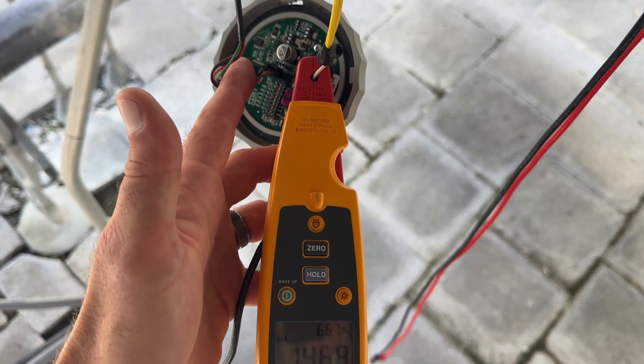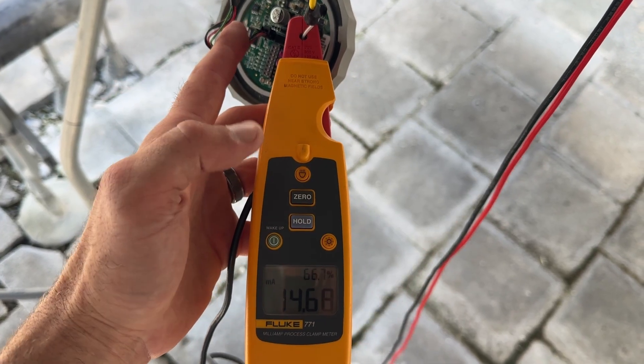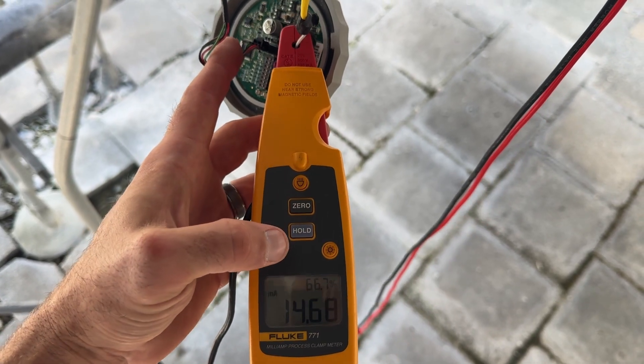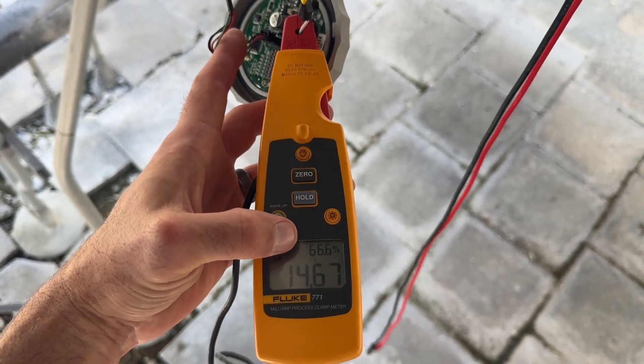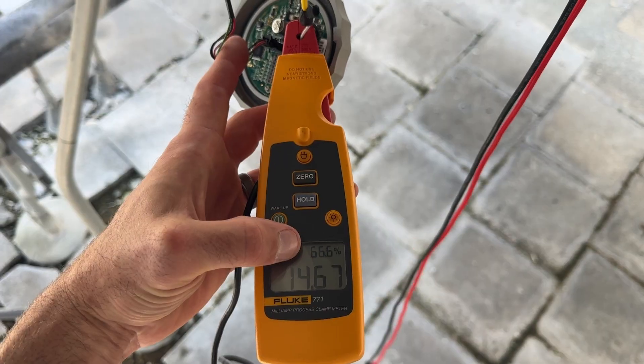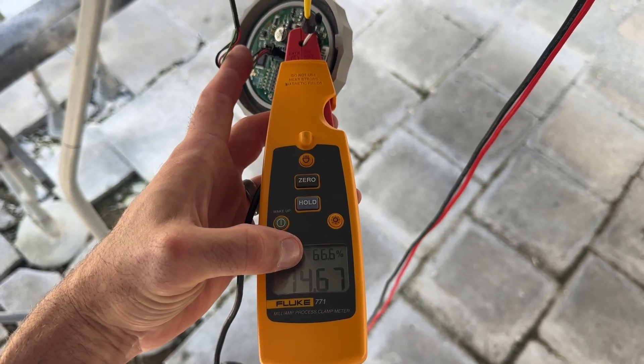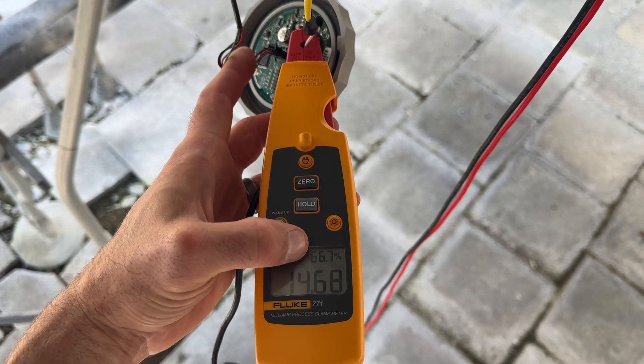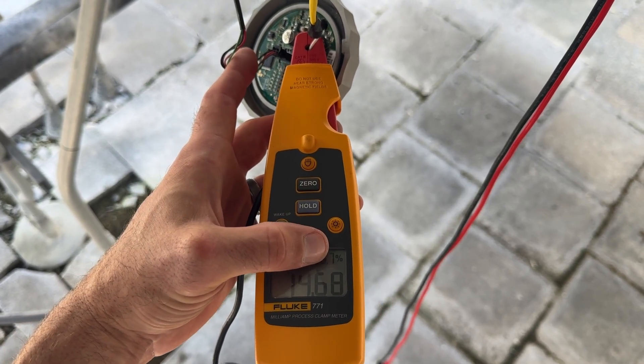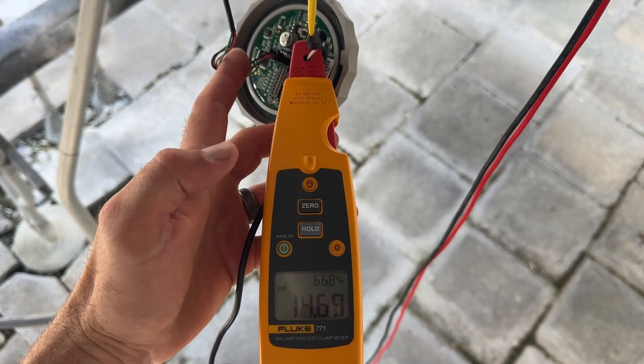What I need is a milliamp reading. And I'll explain why here in a second. But I'm at 14 milliamps, so I should be reading around 70% humidity.